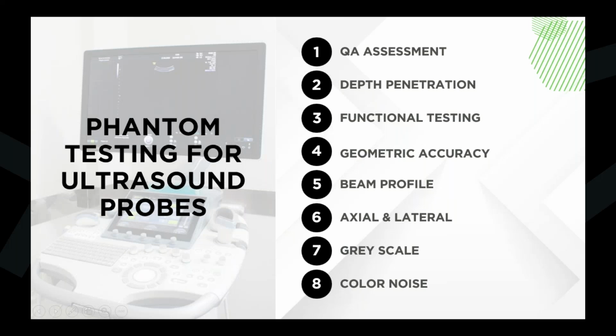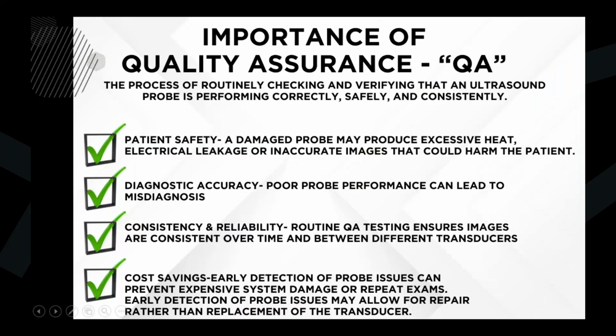All right, important issues for quality assurance tests. One, and the most important one, is patient safety. A damaged probe may produce excessive heat, electrical leakage, or inaccurate images that could harm the patient.